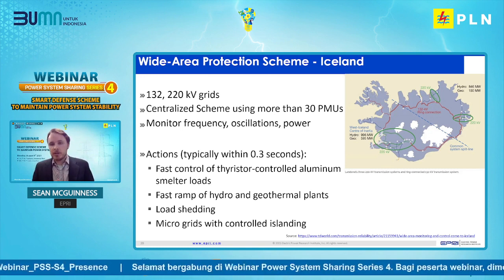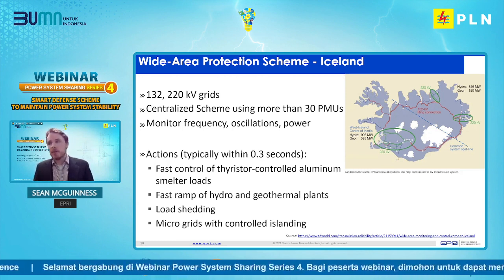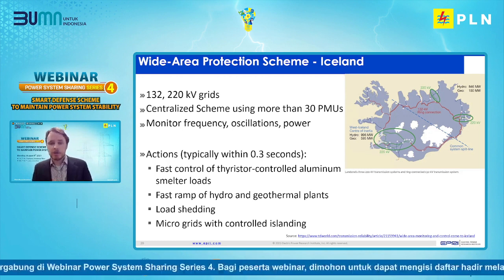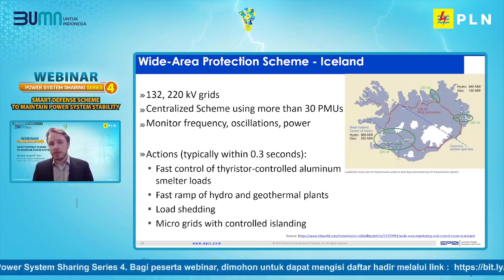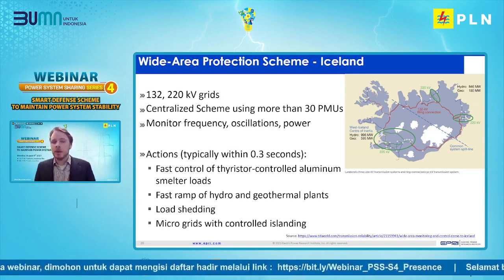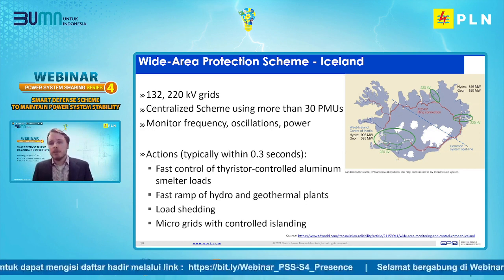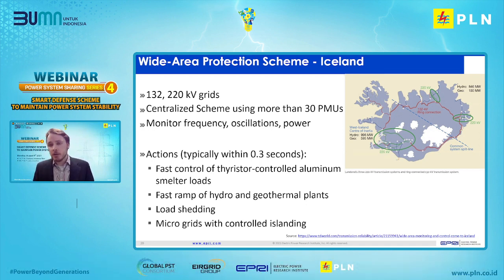Because this is a centralized scheme, it relies on very high bandwidth fiber optic communications. As I mentioned, everything occurs within 0.3 seconds. So they allow a maximum latency of about 0.1 seconds each way. So it is a very fast scheme. This scheme began development in 2005. So it has been around for 16 years, but they've built on it year after year after year. And they've really developed an advanced scheme that has worked very successfully for them in the past and prevented blackouts and prevented instability and other such issues.